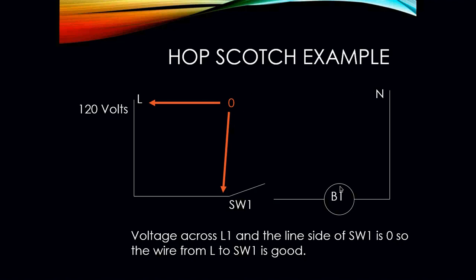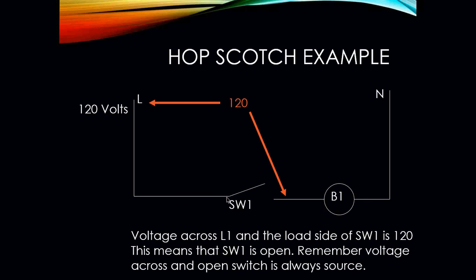We are now going to go across. Again, Hopscotch: we leave one lead at the beginning of the circuit, and then we use the other lead to Hopscotch our way through the circuit, one point right after another. Okay, so voltage across L1 and the line side of the switch is going to indicate 0. So the wire from L1 to switch 1 is still good. The reason we are reading 0 is because this is just one wire. There is no break. There is nothing going on. So my meter is going to pick up a 0 difference in potential. If I go across that switch, I am now reading 120 volts. This means that switch 1 is open. Remember, voltage across an open switch is always source voltage.